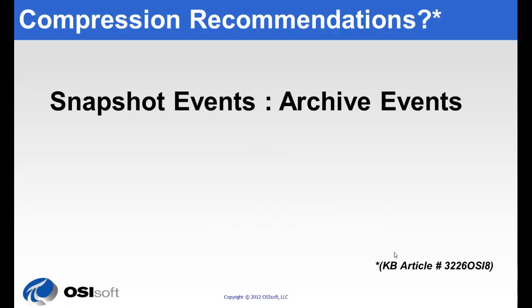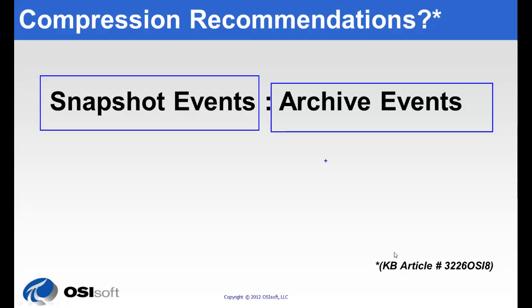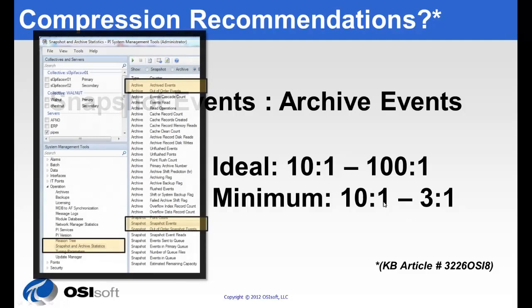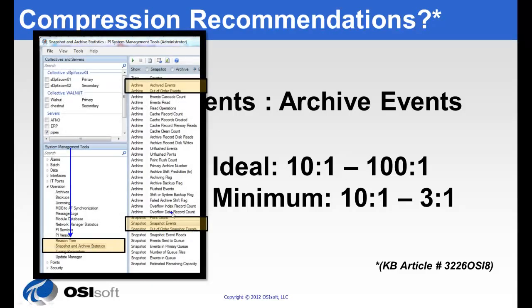Compression settings, we recommend this based on a ratio of the snapshot events to the archive events. Ideally, this is going to be a ratio of 10 to 1 or 100 to 1, and at minimum it should be a ratio of 10 to 1 or 3 to 1. Anything less than that is going to be pretty hard on the PI server. To check this, you can open up system management tools and go to snapshot and archive statistics and look at snapshot events and archived events to get your ratio.